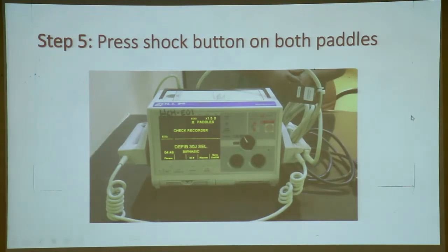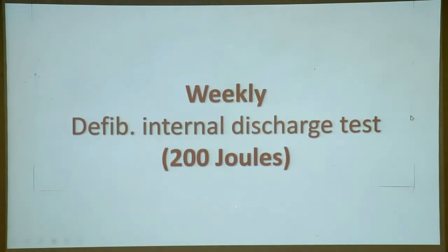Now after you have done this, you do a weekly test, and this is very important because the company doesn't recommend giving 200 joules through the machine every day, as that much energy can spoil the internal parts of the defibrillator. So every day you cannot do it. We do a low energy test every day, just 30 joules. This is not recommended or written by the company.